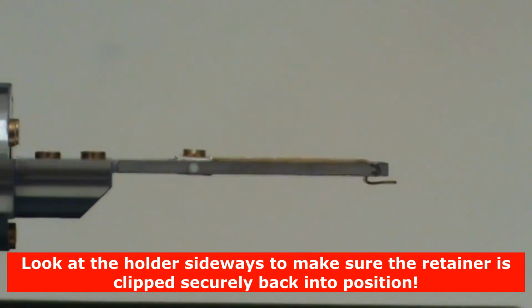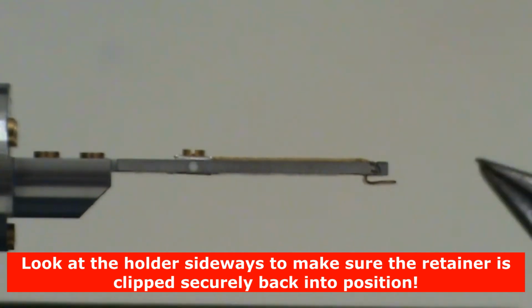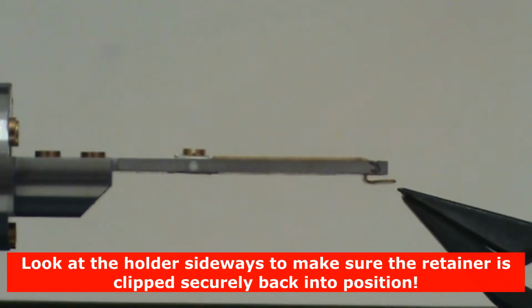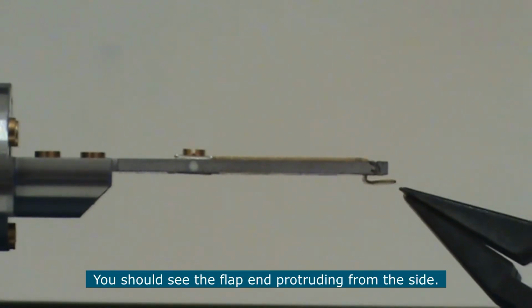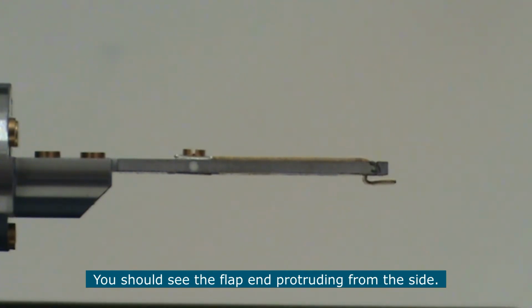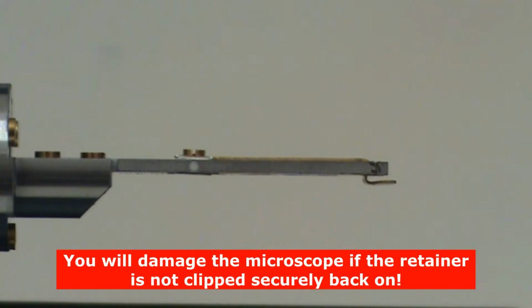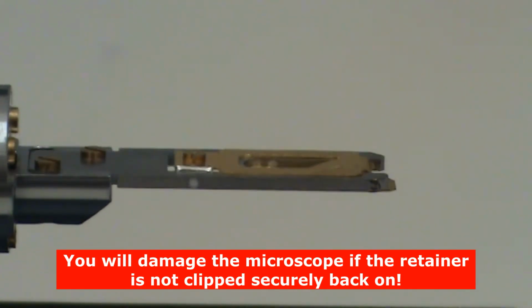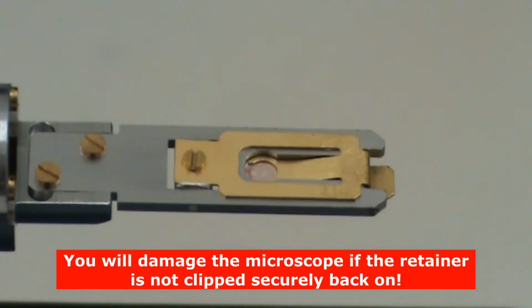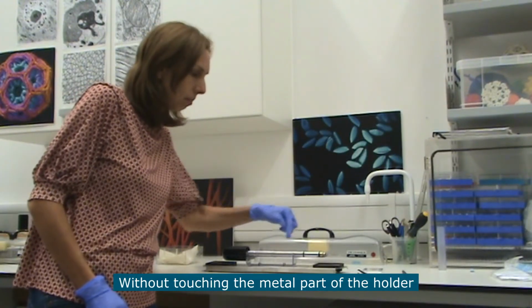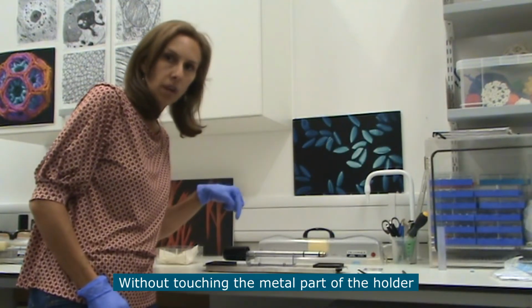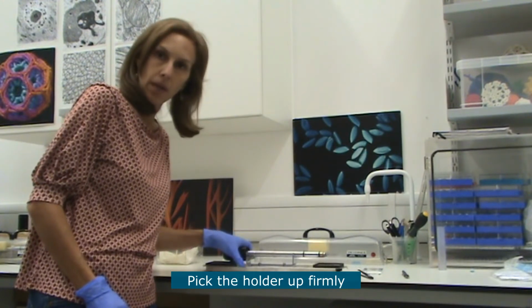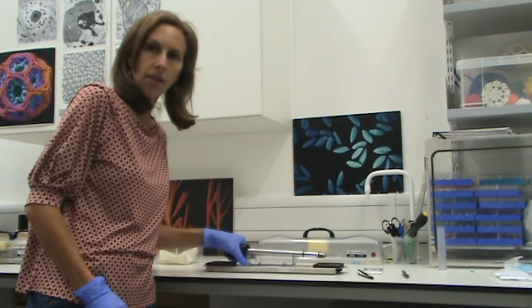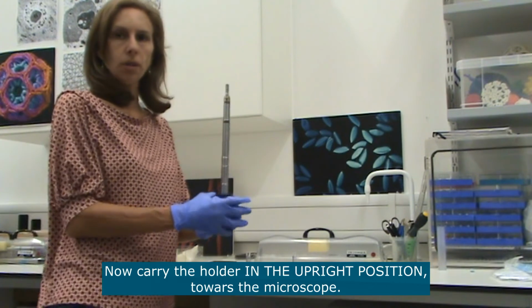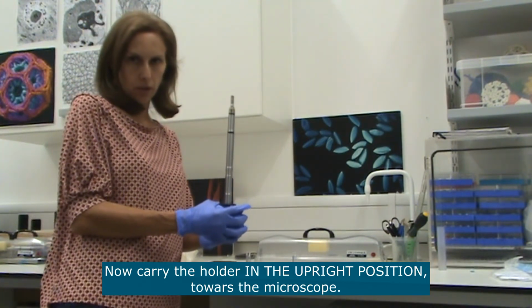If you turn the holder sideways, you should see that the flap is nicely clipped because it's protruding to this side. It's very, very important that this flap is really nicely clipped. Otherwise, when you insert your sample on the microscope, you will damage the microscope. Without touching the metal part of the holder, pick it up firmly and carry it to the microscope, always holding it in the upright position.